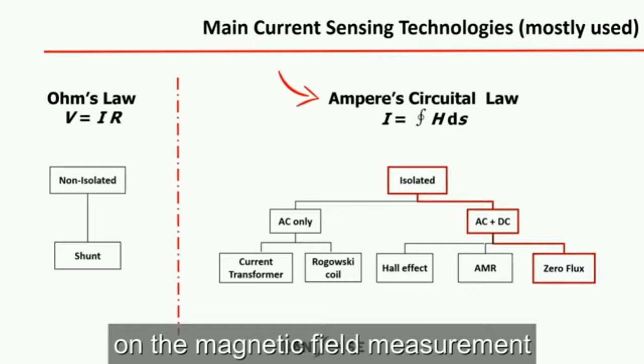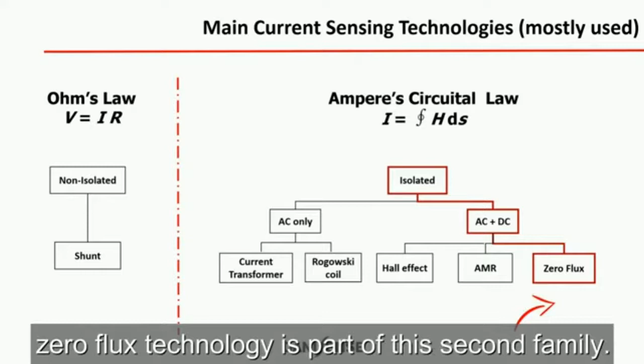First, let's have a quick look at the most commonly used current sensing technologies. There are two main families. The first is based on Ohm's law, also known as shunt. The second is based on measuring the magnetic field generated by the circulation of current. This technology can measure AC only, like a current transformer, or both AC and DC. As you can see in the diagram, zero flux technology is part of this second family.